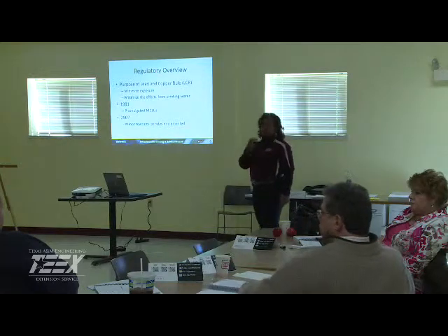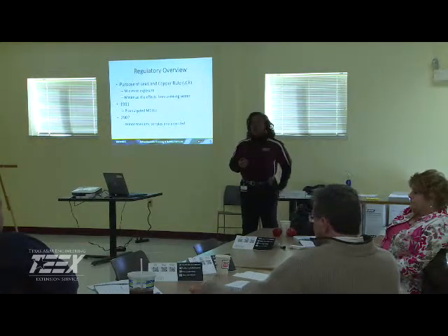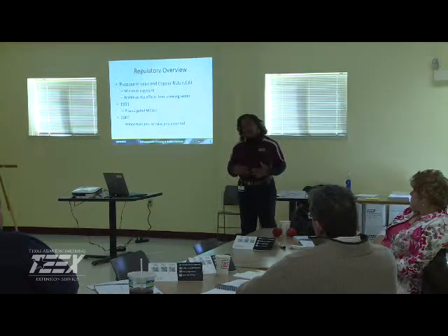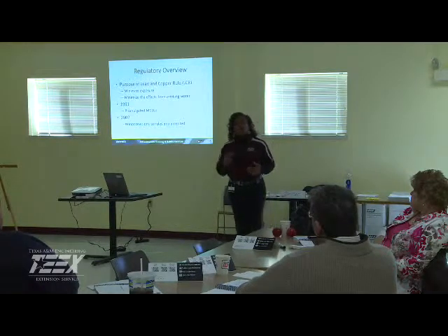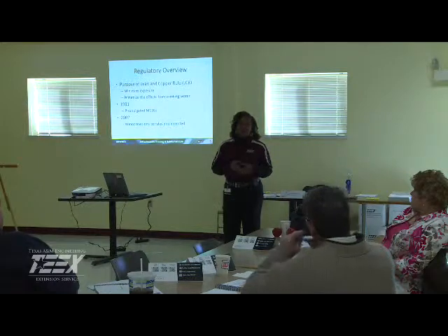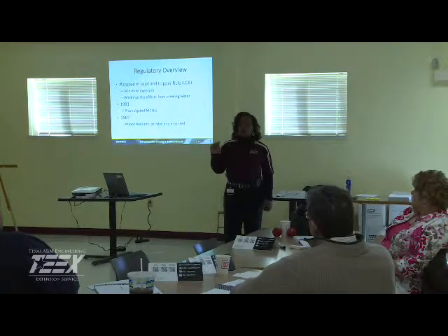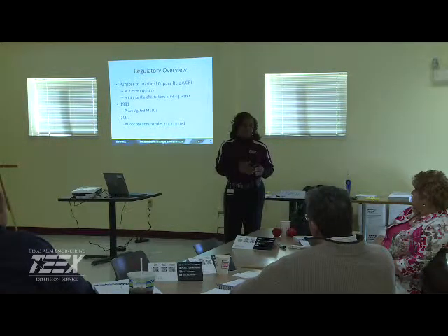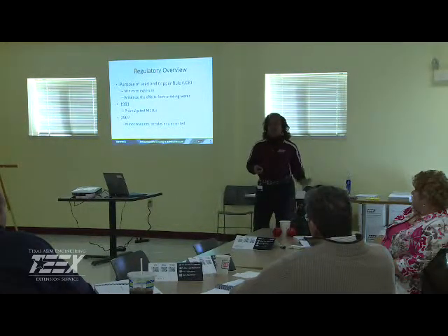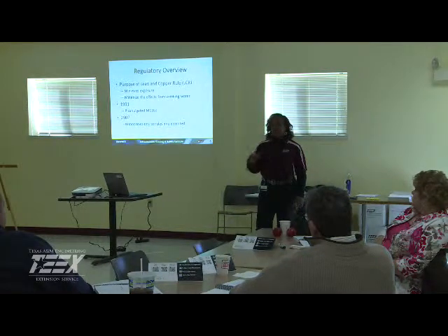So copper by itself is a concern too, because we still use copper piping. There are still some health effects from copper, such as gastroenteritis and things like that, when you're over the maximum contaminant level, which is 1.3. And the way I look at any contaminant, if there's a huge MCL, anything over 1, then it's not going to be as serious on health as, let's say, arsenic at 0.01 milligrams per liter. That's a big difference. The smaller the MCL, the more potent that contaminant is as far as health concern.